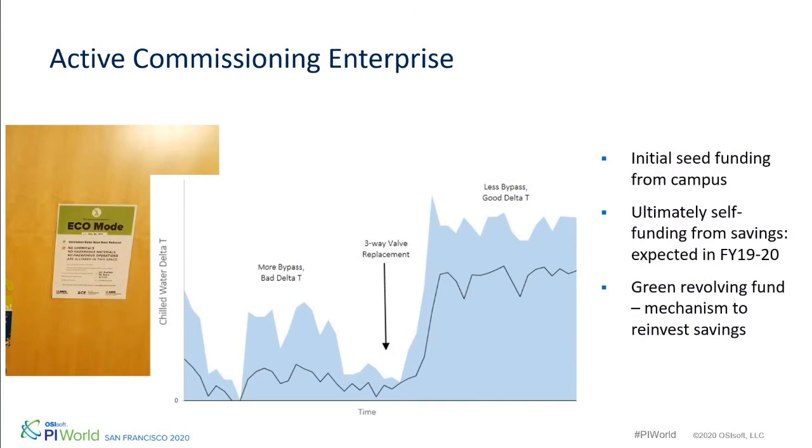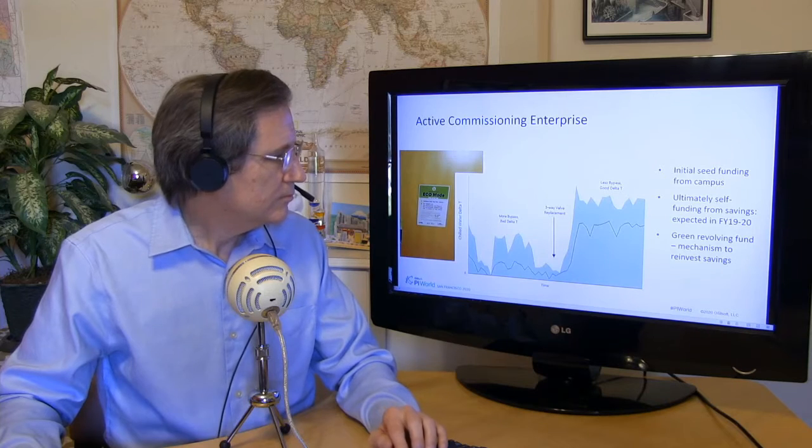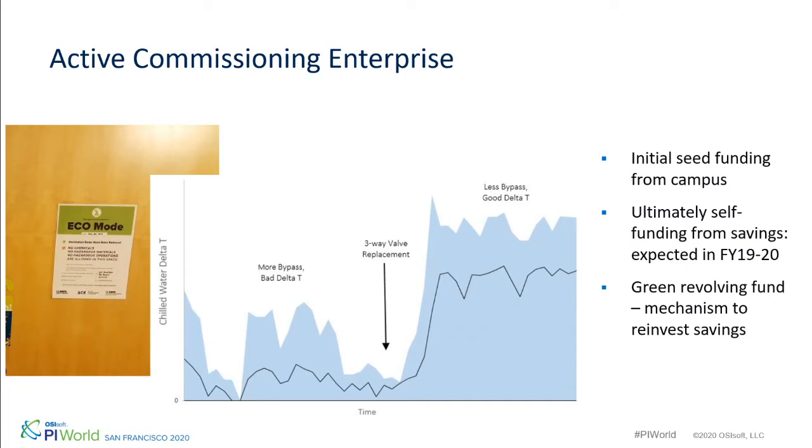We've got some slides. We're looking at the delta T screen. Now you were saying that this type of comparison was just something you weren't able to do before? Yeah, that's correct. Just having a single view of all the buildings' delta T and flow, and then how the plant is behaving as a result, was not something we were able to see before. So the power really is for the plant. If the chiller is not running efficiently, the plant can then identify why, whereas previously it was a total black box.